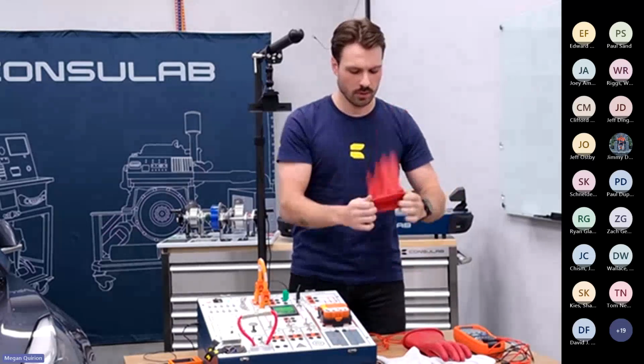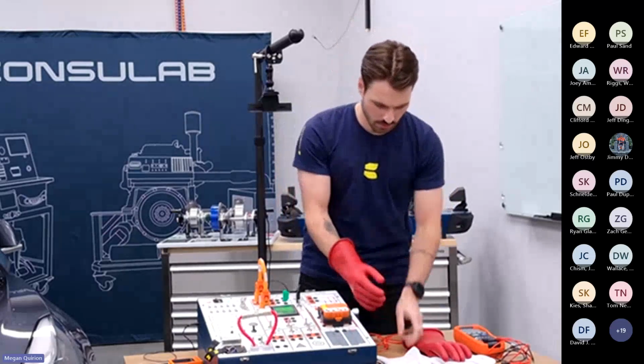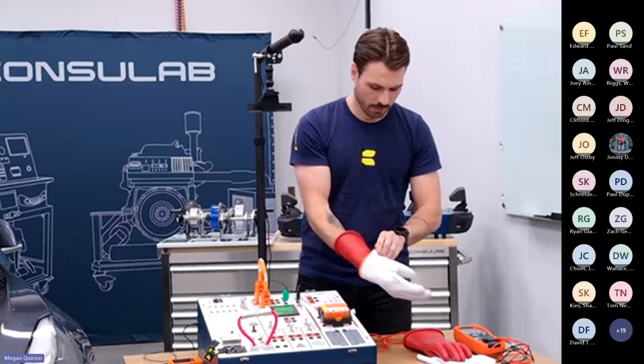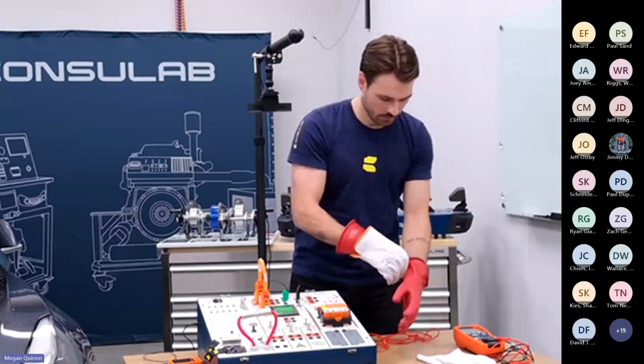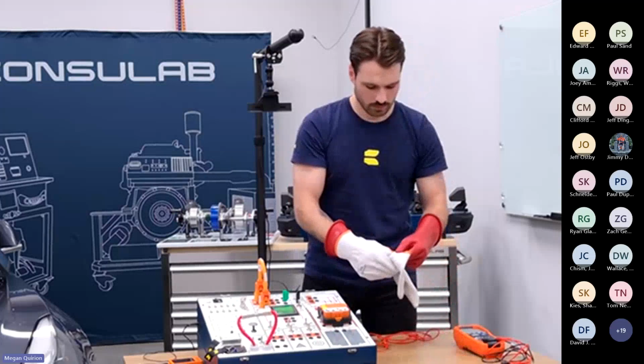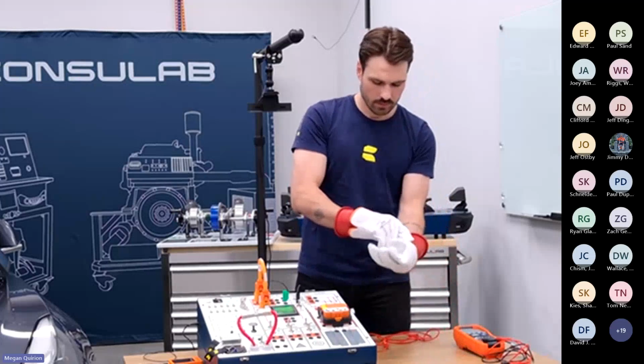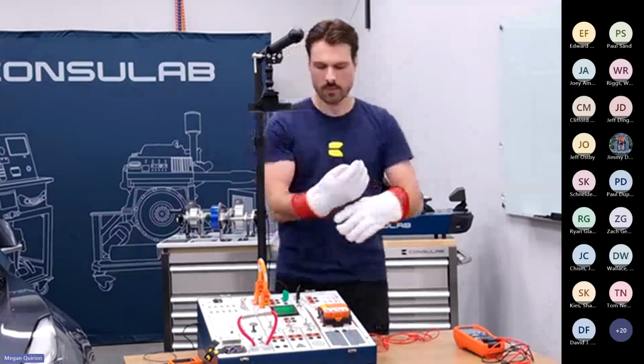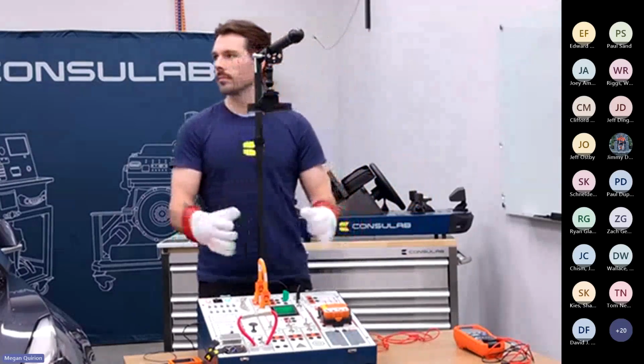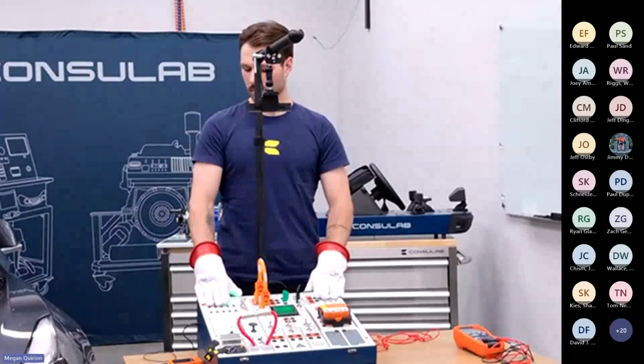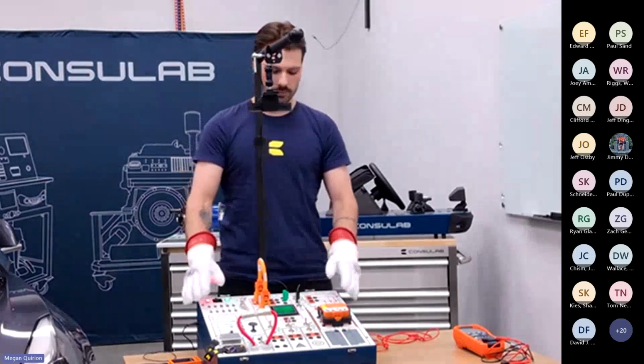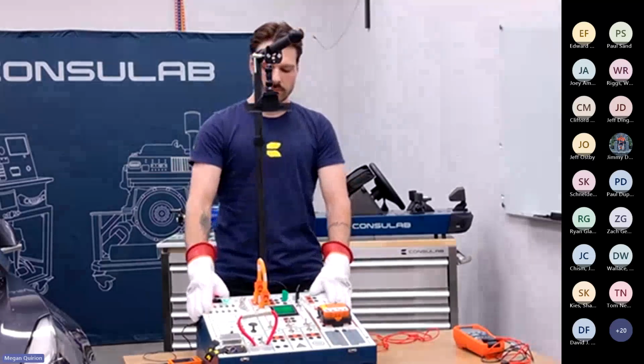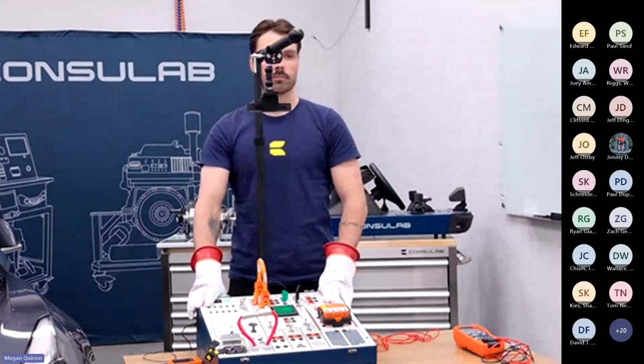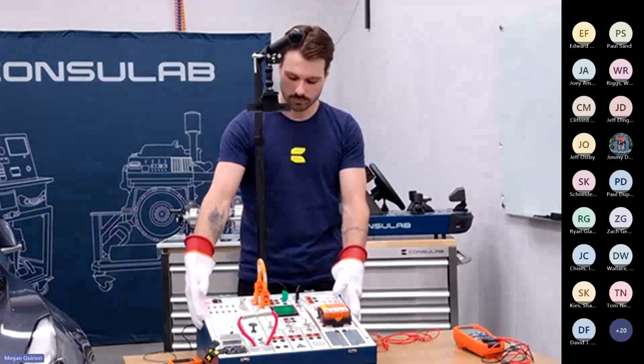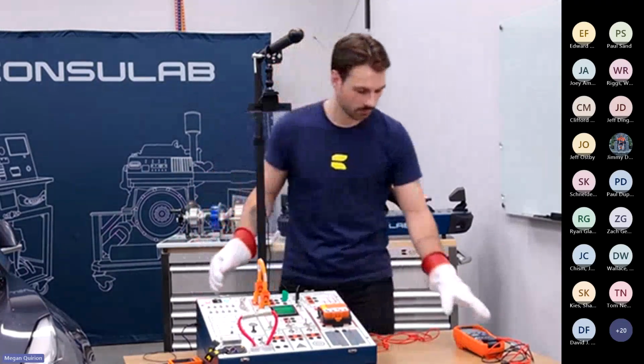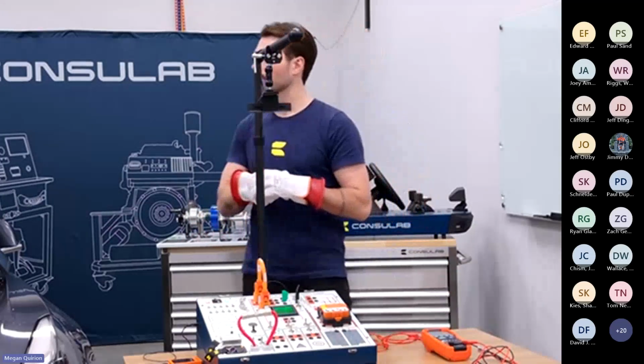to ensure that they're suitable for servicing. Now, the 400 trainer that we're using here is 400 volts, so we do require the safety PPE in doing so. But at the same time, we want to make sure that the students are still safe. Even if they make a mistake with this trainer, even if they touch the high voltage 400 volts, it's less than 2 milliamps. So it fools the equipment into thinking that we have the high voltage there, but there's very low risk of getting any kind of real shock, other than maybe something like a static shock.